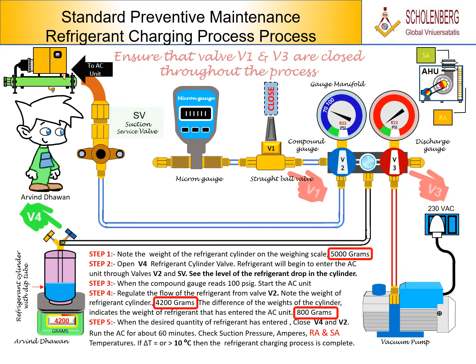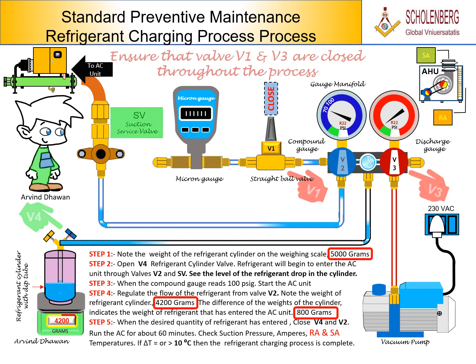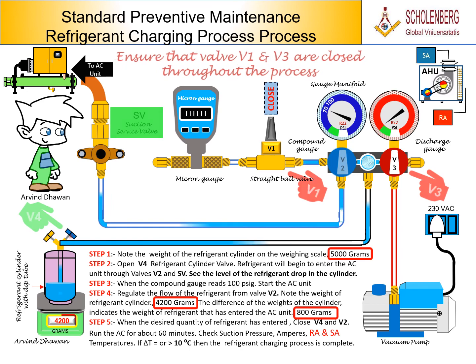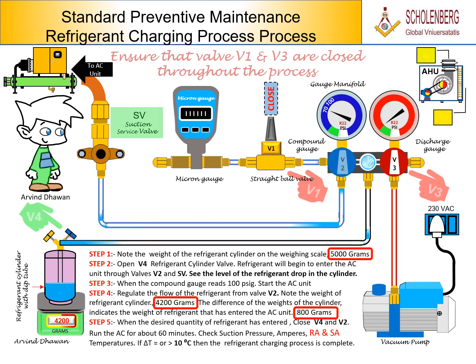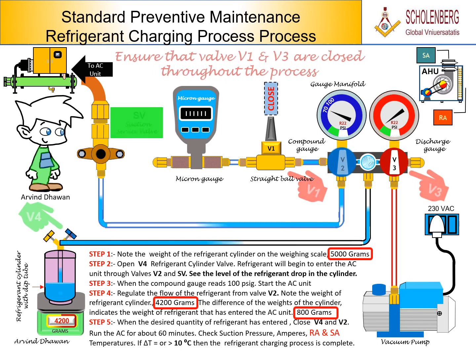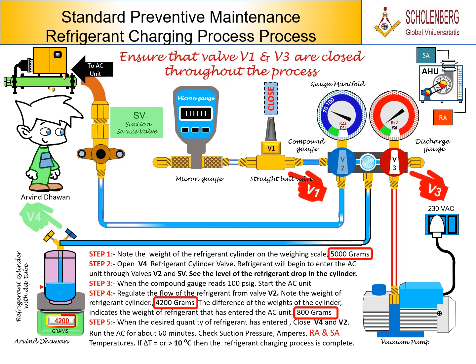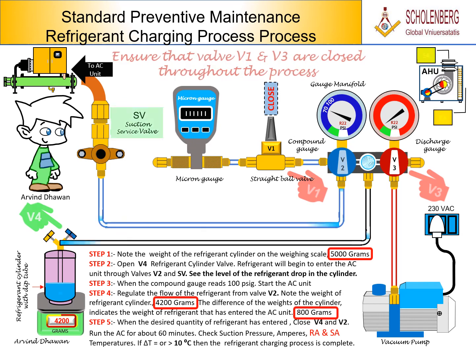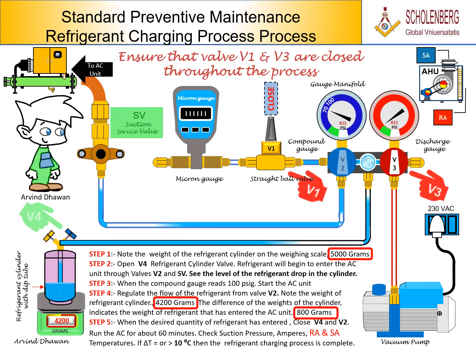Step 5. When the desired quantity of refrigerant has entered, close V4 and V2. Run the AC for about 60 minutes. Check suction pressure, amperes, RA, and SA temperatures. If delta T is equal to or greater than 10 degrees centigrade, then the refrigerant charging process is complete.